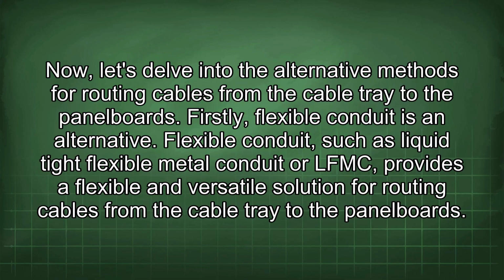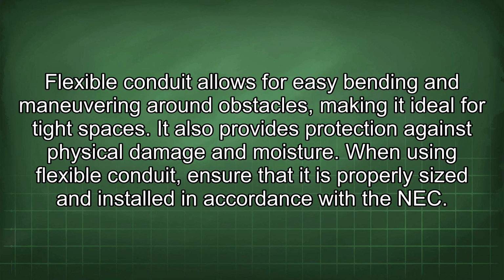Flexible conduit, such as liquid-tight flexible metal conduit or LFMC, provides a flexible and versatile solution for routing cables from the cable tray to the panel boards. Flexible conduit allows for easy bending and maneuvering around obstacles, making it ideal for tight spaces. It also provides protection against physical damage and moisture. When using flexible conduit, ensure that it is properly sized and installed in accordance with the NEC.